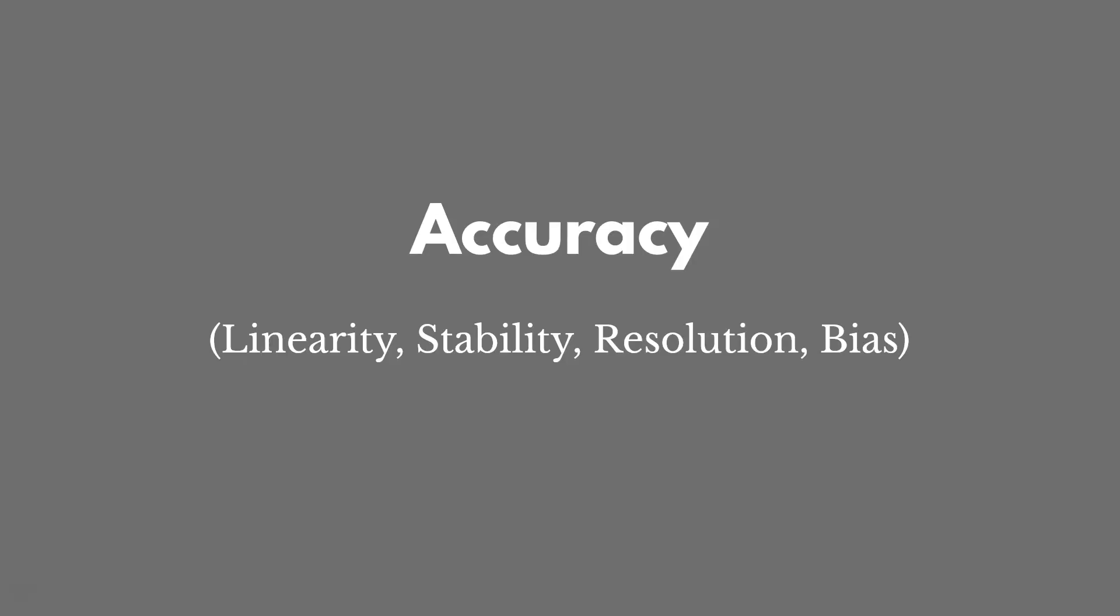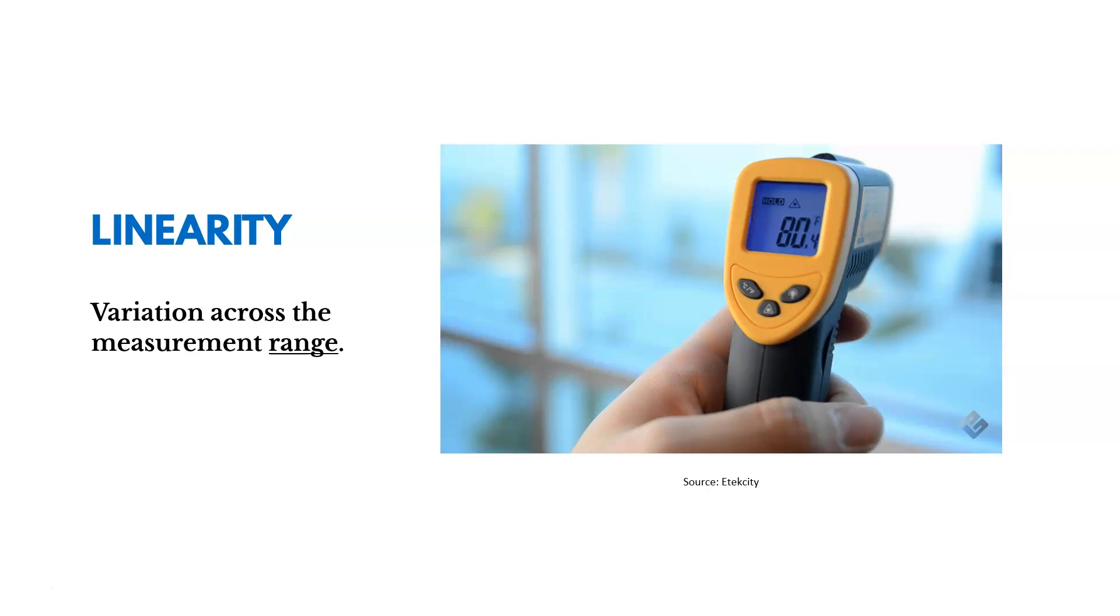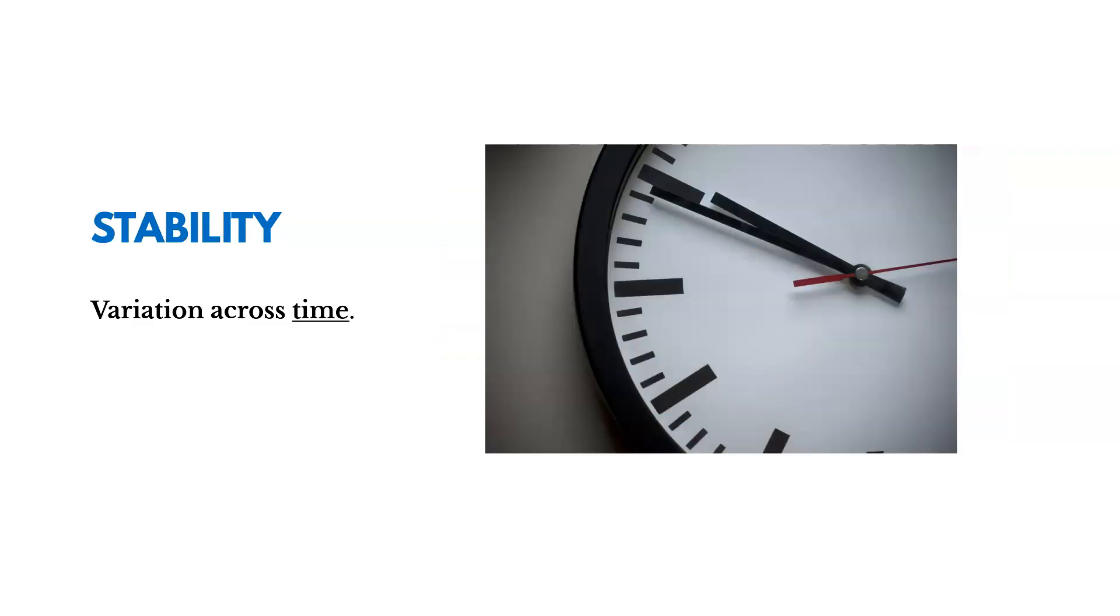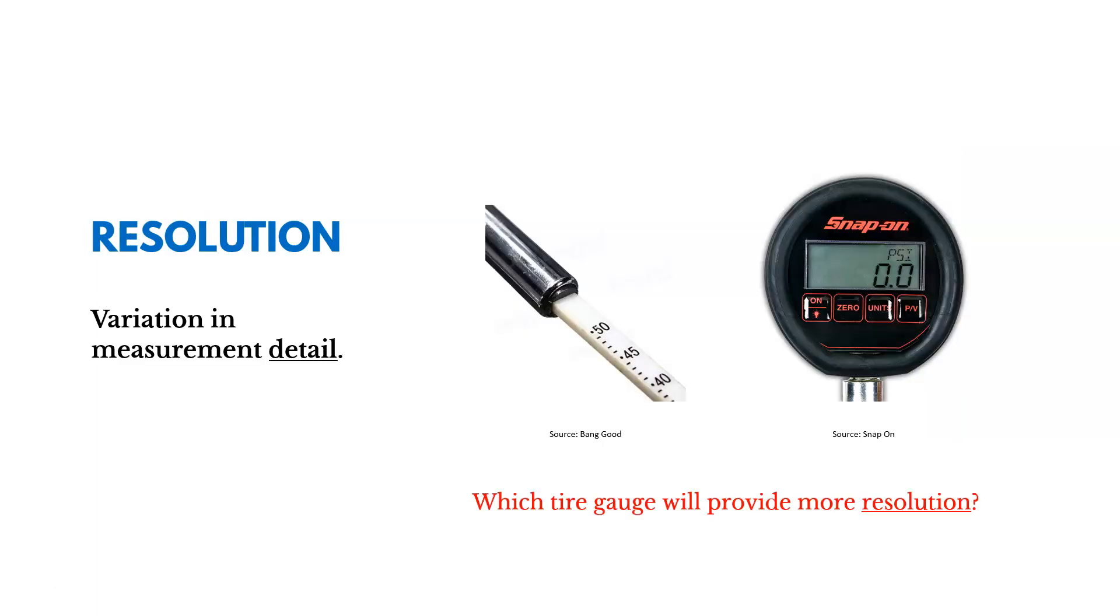Now diving a little deeper here into accuracy again with these four goals. We have linearity, which measures variation across the measurement range. We want to minimize that. So again, the temperature example is getting accurate readings in both low and high temperatures, or low and high pressures, if we're measuring pressure. And the stability is monitoring and minimizing variation across time, making sure we have stable measurements. And then resolution is variation in measurement detail. Now, if you take a look at these two gauges, the question you could ask is which tire gauge would provide more resolution. It would be that digital gauge. It's much harder to see the detail in the manual gauge there.